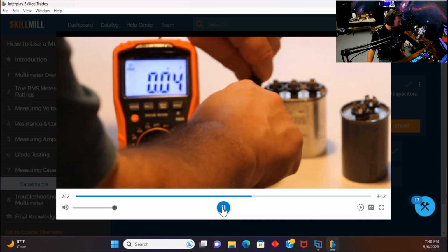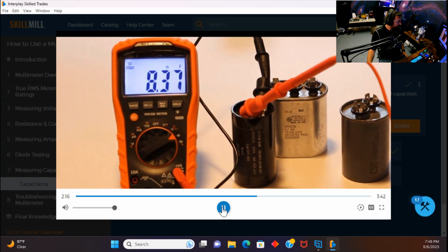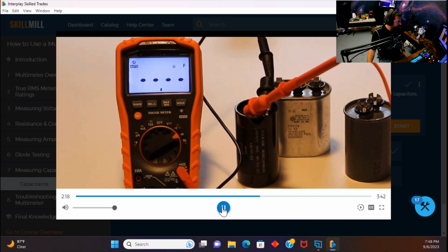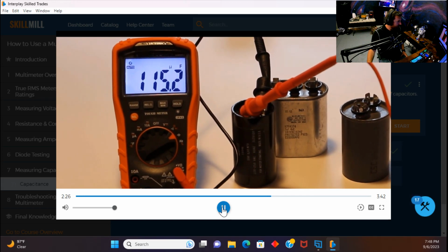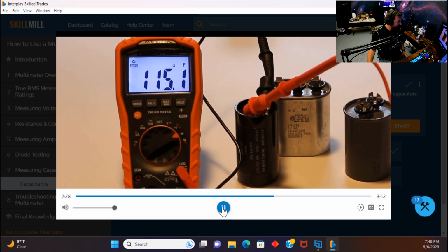So when I place it across these terminals, we should get a substantially higher reading here on the meter. And we'll just give it a second to calculate. And we see that we have about 116 microfarads on the start capacitor. Now, a bad capacitor would produce an unusually low reading or possibly no reading at all, 0 on the display.